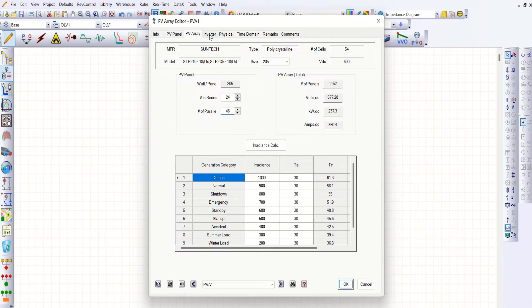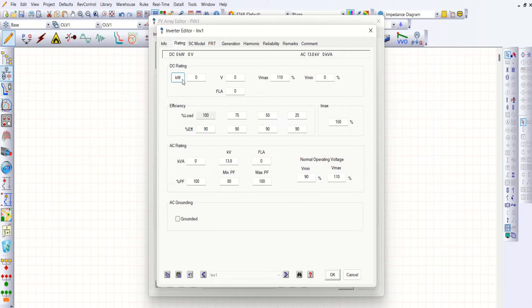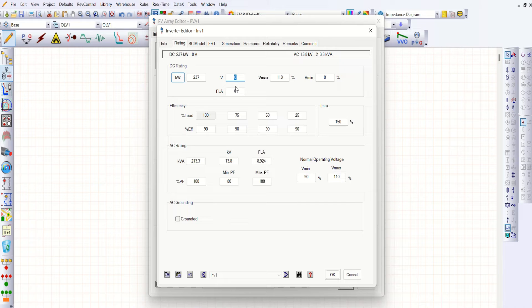Then go to inverter. Whatever values we have selected — DC voltage of 677V, kilowatt of 237, about 350 amps DC — use those for the inverter. Inverter rating is based on your kilowatt here. I just set DC input to 237, so that I may get 213 kVA inverter output. Similarly, the voltage I got is about 677V, so I'll fix it to 650. The voltage on the AC side is — as you've noticed — the secondary side of the transformer is 0.690kV, so let me stick to 0.690kV here.